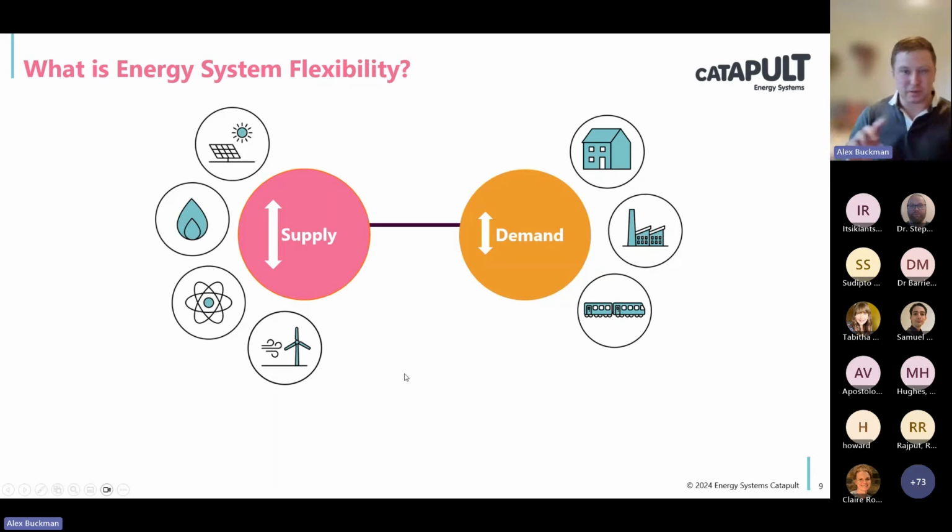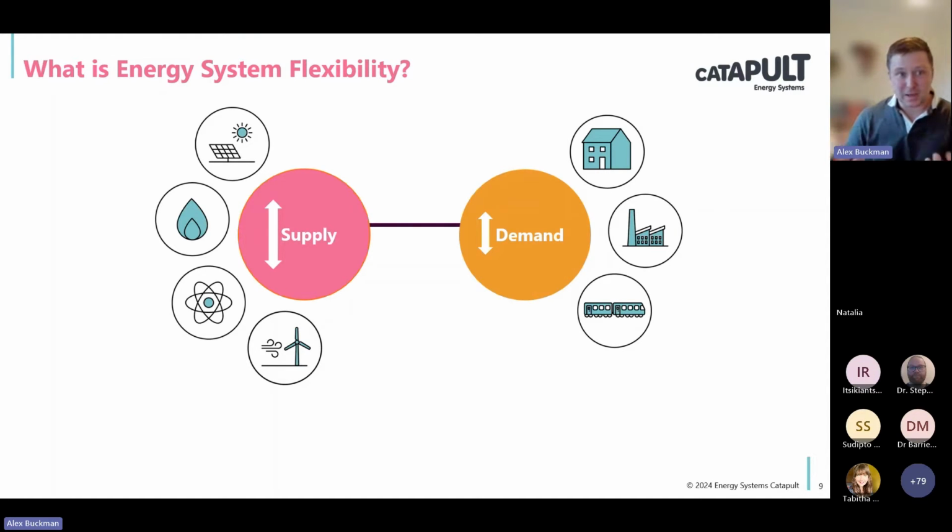So in between your supply and demand, you've got the pipes and the wires, and loads of other fairly expensive infrastructure in between those. That's the way that we typically transmit energy from your supply to your demand. And so it importantly has to meet the most extraordinary circumstances. So when we specify how big your pipes and wires need to be, they need to be sized for those 1 in 20 style winters. So those winters that are extraordinary compared to other winters. And that's really important, because that is quite an expensive criteria to meet when you're talking about quite big infrastructure in some places.